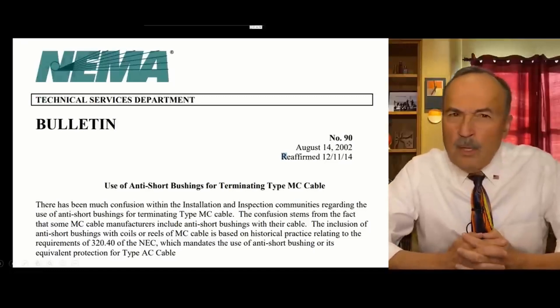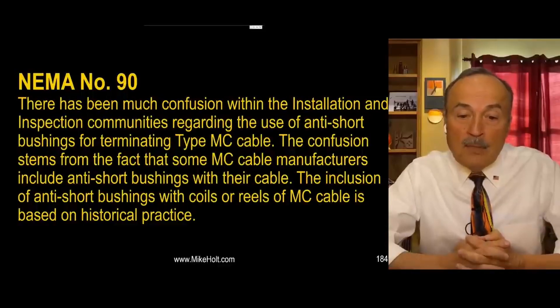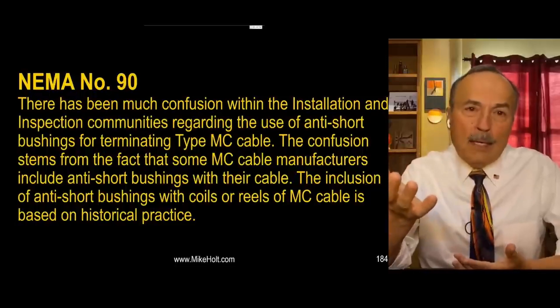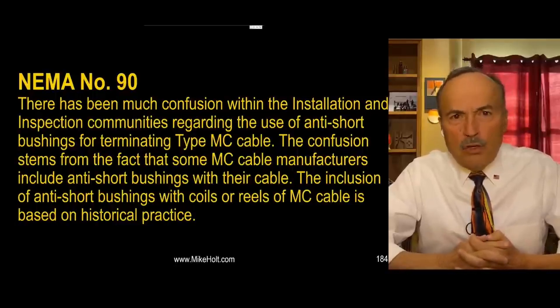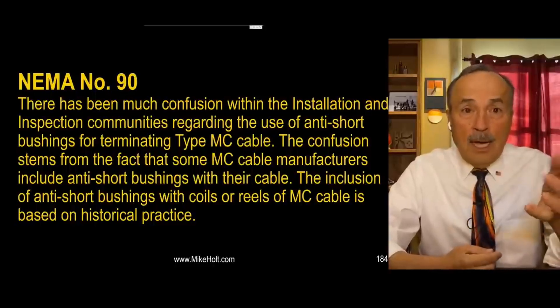Let's go to the NEMA bulletin on the use of anti-short bushings for terminating type MC cable. It reads: 'There has been much confusion within the installation and inspection communities regarding the use of anti-short bushings in terminations for type MC cable. The confusion stems from the fact that some MC cable manufacturers include anti-short bushings with the cable.' They include them because people yell at manufacturers if they don't, so they try to be nice - but they're not code experts.